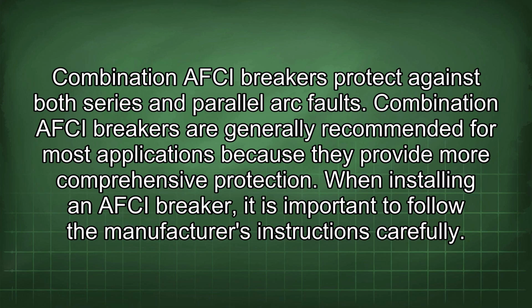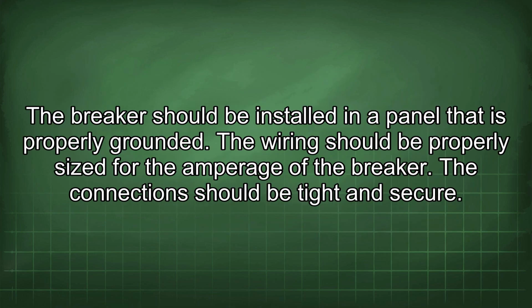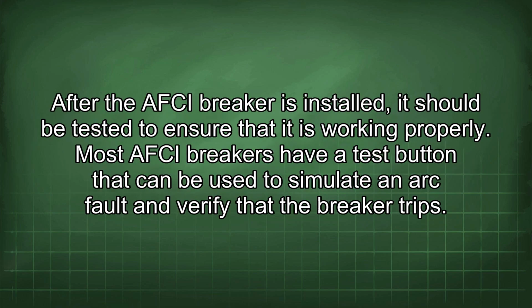When installing an AFCI breaker, it is important to follow the manufacturer's instructions carefully. The breaker should be installed in a panel that is properly grounded. The wiring should be properly sized for the amperage of the breaker. The connection should be tight and secure. After the AFCI breaker is installed, it should be tested to ensure that it is working properly.